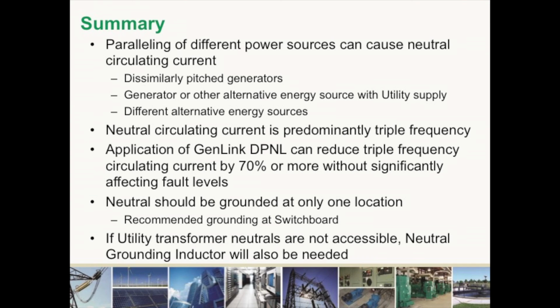So in summary, when you're paralleling different power sources, you can result in neutral circulating currents, either dissimilarly pitched generators, or generators or other alternative energy sources with the utility supply, or different alternative energy sources. So anything that could have a voltage wave shape, a voltage source generator that would have different wave shapes. The neutral circulating current is predominantly triple frequency, so on a 60 hertz it's 180 hertz, 50 hertz it's 150 hertz. We can apply a DPNL that will reduce that triple frequency circulating currents by more than 70%, without affecting fault levels. And the neutrals should be grounded at only one location. And if there are utility transformer neutrals, if they're accessible, we want to run those neutrals through the DPNL and ground the system at one location.